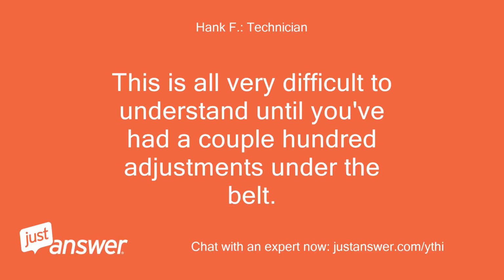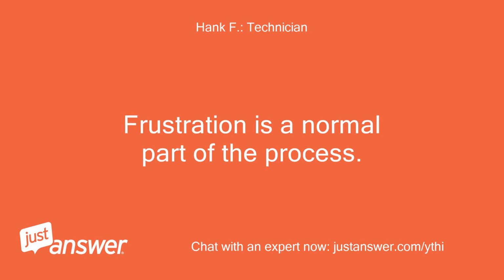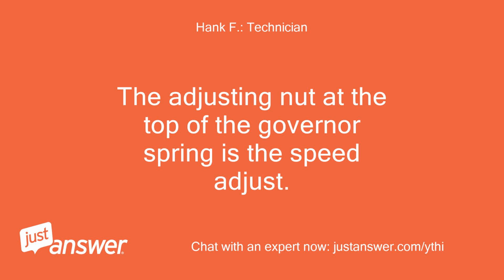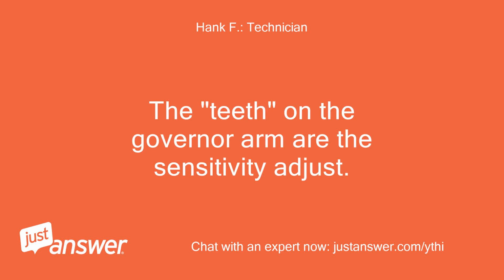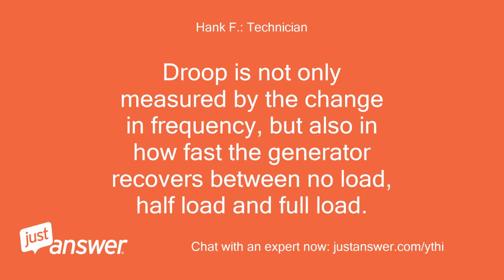This is all very difficult to understand until you've had a couple hundred adjustments under the belt. Frustration is a normal part of the process. The adjusting nut at the top of the governor spring is the speed adjust. The teeth on the governor arm are the sensitivity adjust. Droop is not only measured by the change in frequency, but also in how fast the generator recovers between no load, half load and full load.